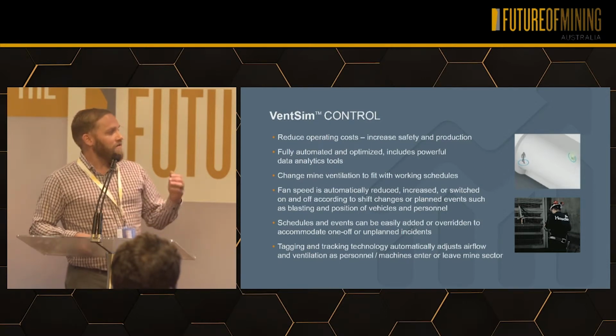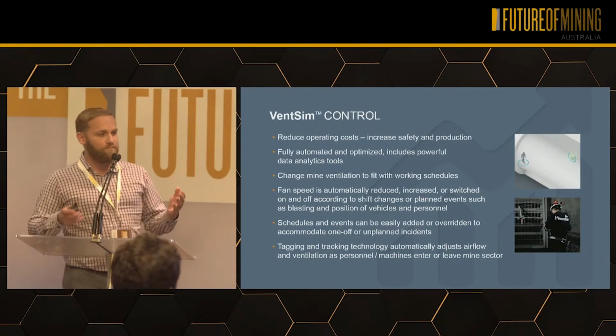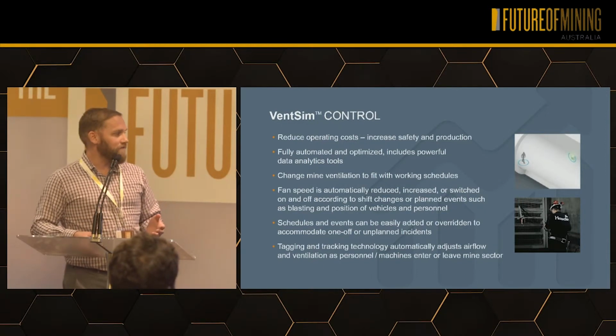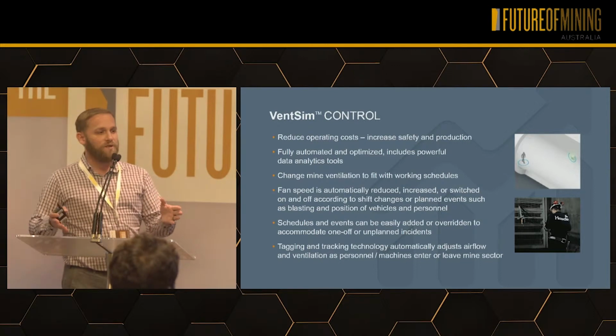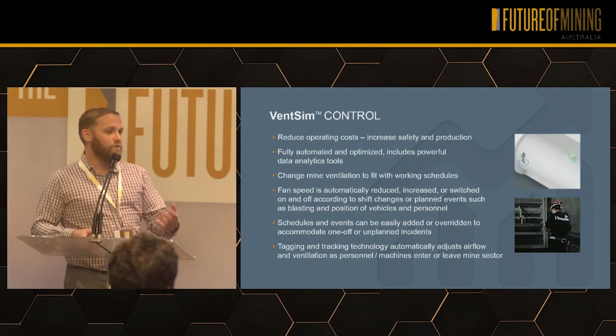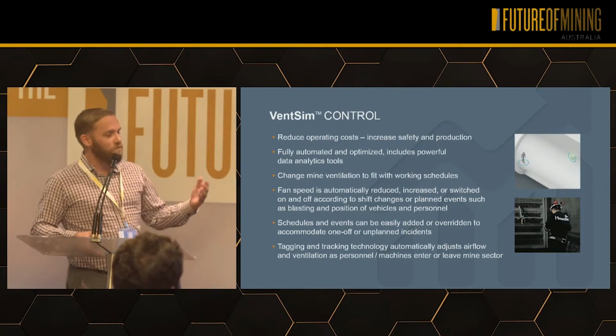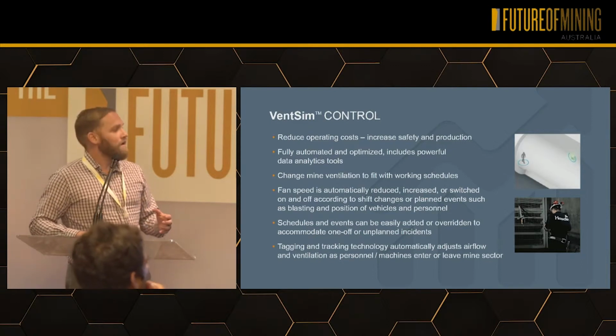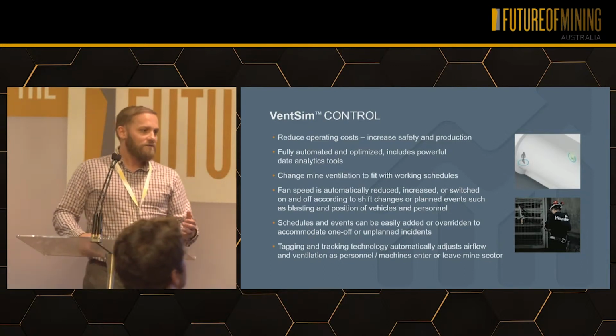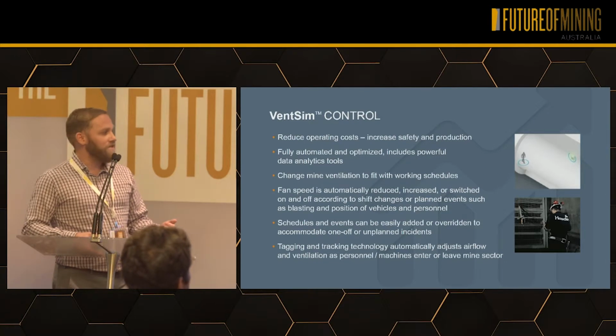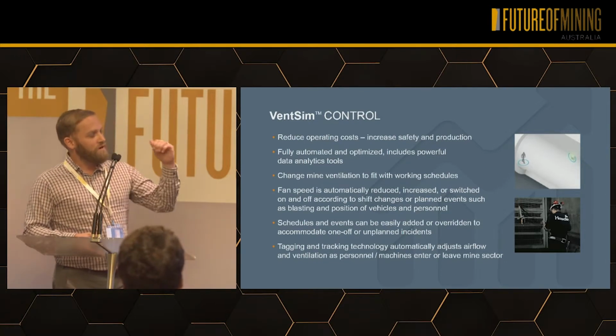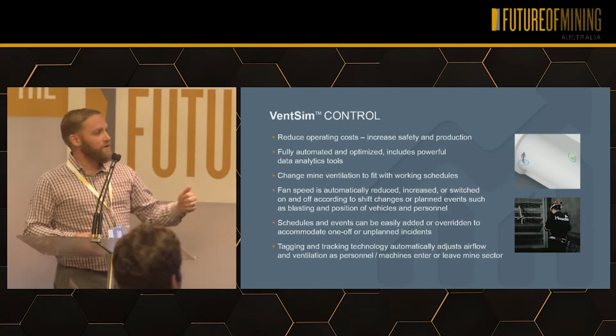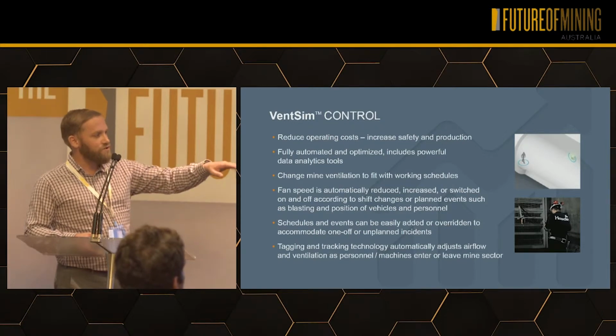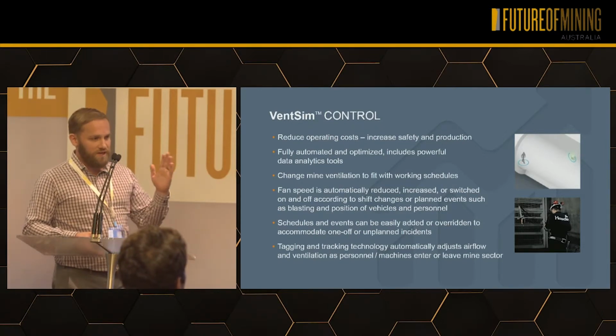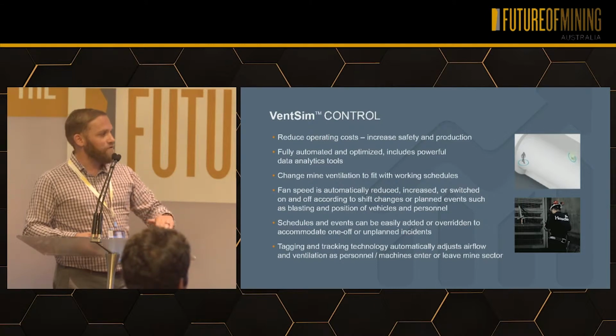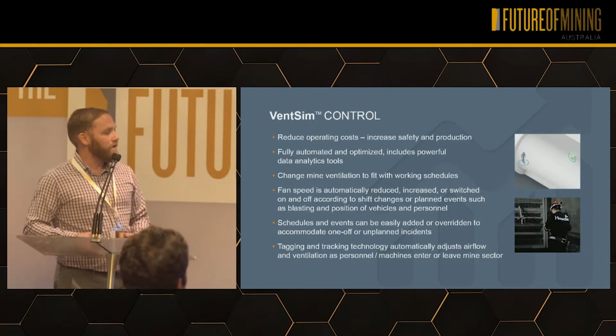The software is able to tell exactly who's underground at any given time, know exactly where they are within the mine, and know what their ventilation requirement is. The software can manage that ventilation to make sure wherever those people are, they're getting the air that's needed, through control of fans underground or on the surface, and control of airflow regulators to give automatic adjustment for each mining level where air is needed.